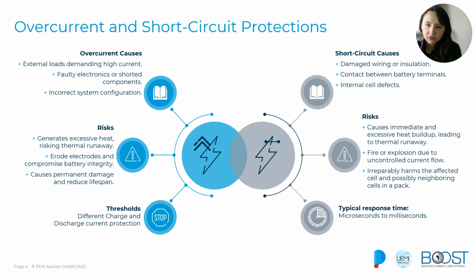Then we have the current protections, and we have overcurrent or short circuit protections. The overcurrent occurs when our system is demanding more current than what the battery is designed to handle. This can happen due to external loads that demand too much current. Also, it can happen with faulty electronic systems, or when we have those systems misconfigured in regard to the maximum capabilities of our battery.